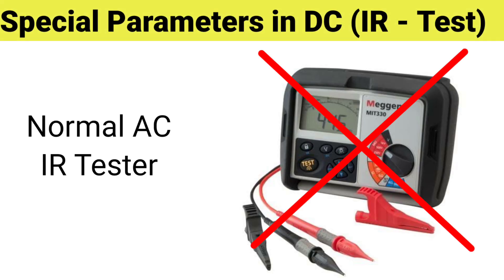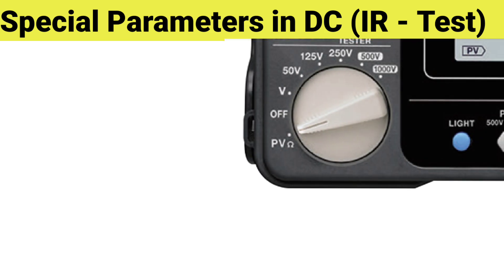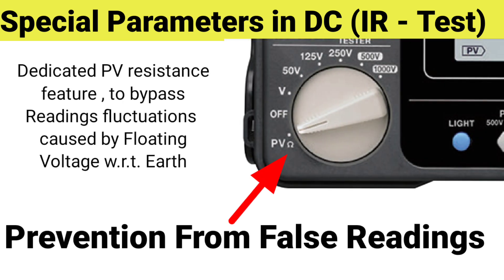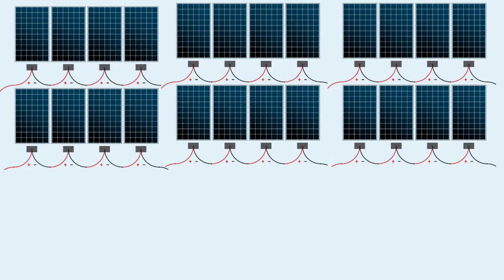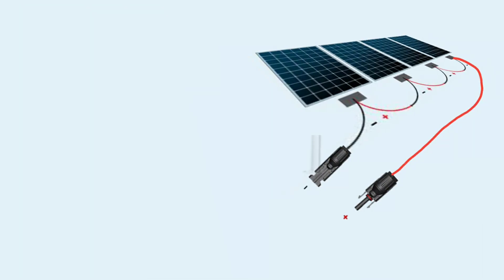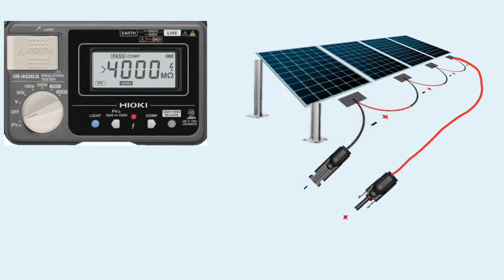Unlike a normal IR tester, this device has a special PV resistance parameter to bypass the fluctuation caused by the solar string, as even open strings have floating voltages with respect to earth which may generate incorrect readings on a normal IR tester. First, select the array you want to test and open the string you want to test.